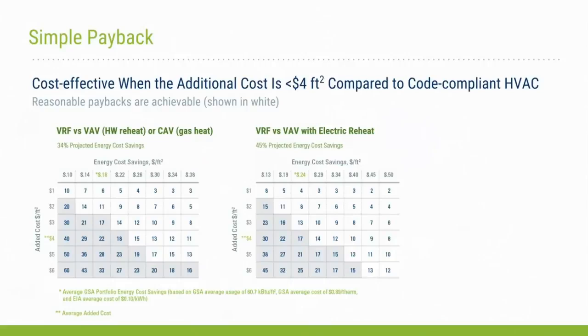An important consideration for the selection of a system is its cost effectiveness. And these two charts show number of years required for simple payback. The y-axis on both of the charts lists incremental cost. The columns show various energy cost savings values. The table on the left compares VRF systems to VAV systems that have hot water reheat and constant air volume systems with gas heat. The table on the right compares VRF to VAV systems with electric reheat.